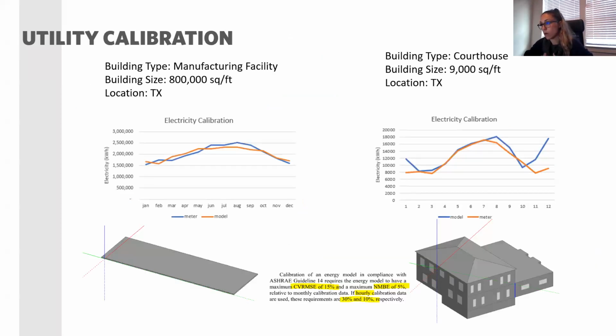So when we decide on the route to go, the bin route, the calibration route, or the energy model route, that means the first thing we need to do is utility calibration. These two examples are to show different sizes. One was an 800,000 square feet industrial building, the other was a 9,000 square feet courthouse, and we still had to comply with, especially with Level 3, ASHRAE Guideline 14 in terms of accuracy. For mean bias error, it needs to be within 5%, and CV(RMSE) needs to be within 15%.